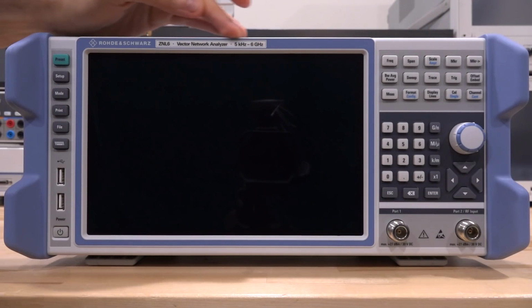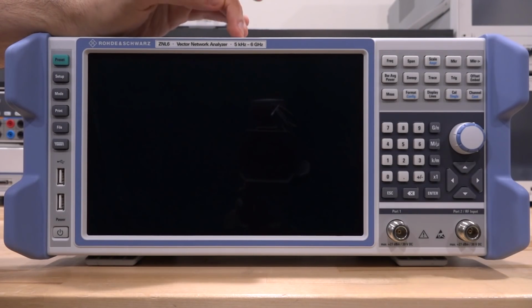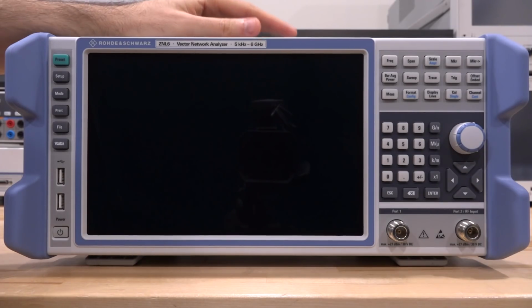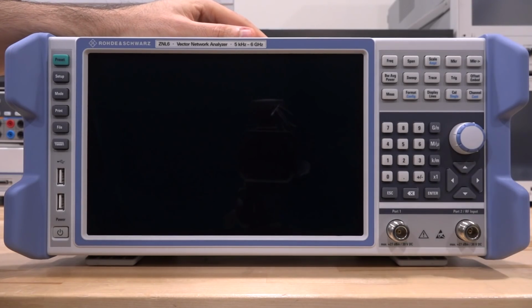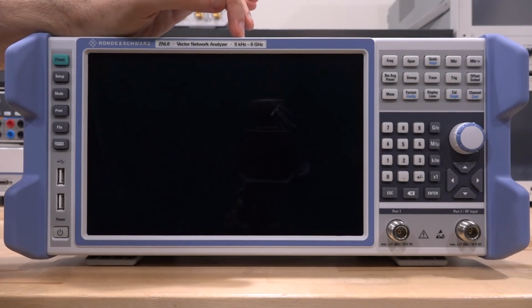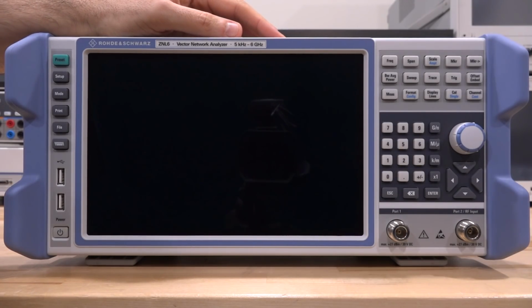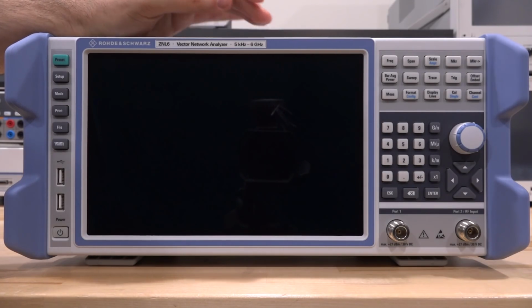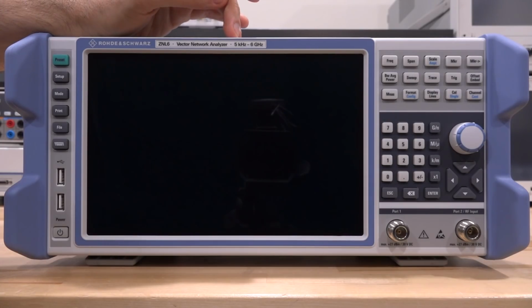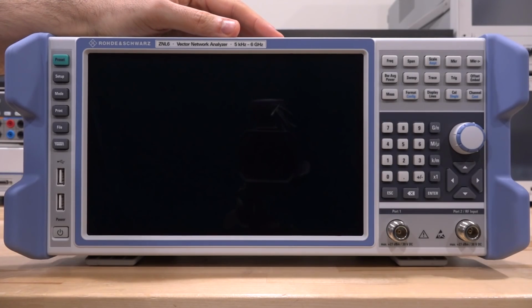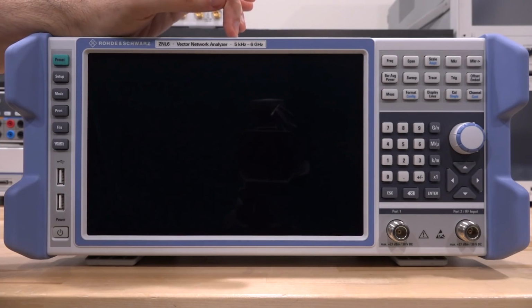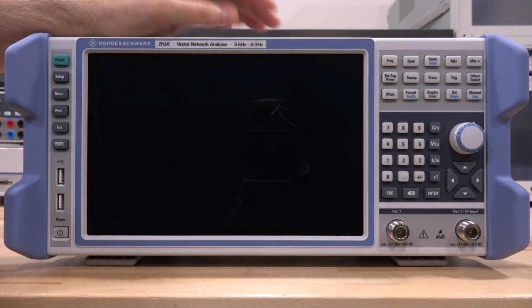And if you look at the frequency range over here, this can go from 5 kilohertz to 6 gigahertz. This is a fully configured instrument with all the options, and the ZNLE could only go down to 1 megahertz. And that difference makes a really big difference in some of the other applications. If you're looking at broadband amplifiers or some backplane and you want to make sure that you have a good connection at low frequencies, or if you're measuring passives and you want to make sure they don't resonate for, let's say, power supply decoupling and so on, being able to go down to 5 kilohertz is quite important.